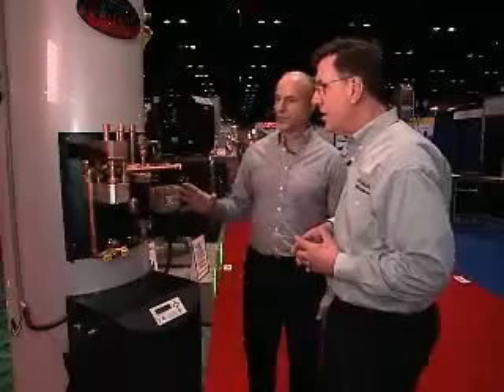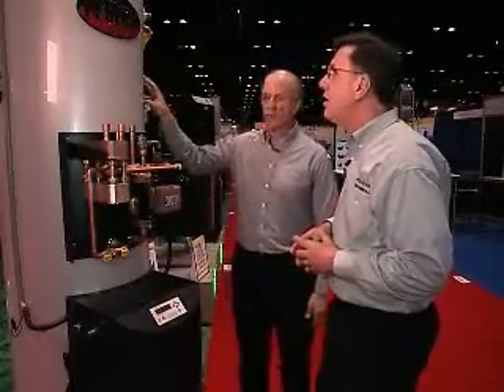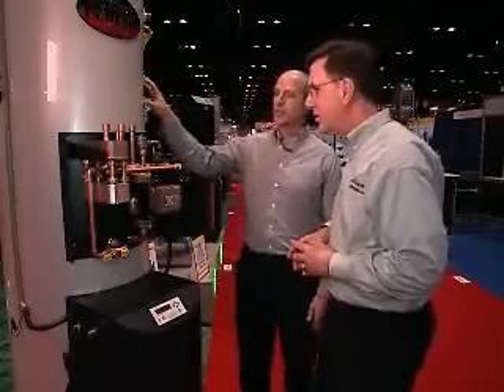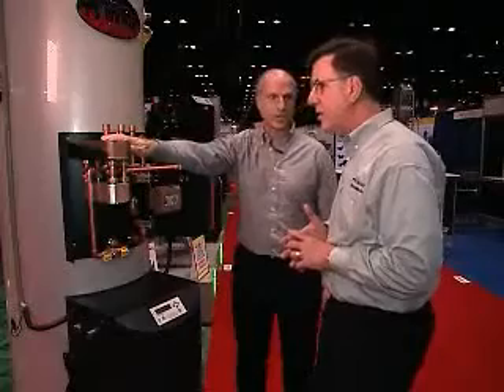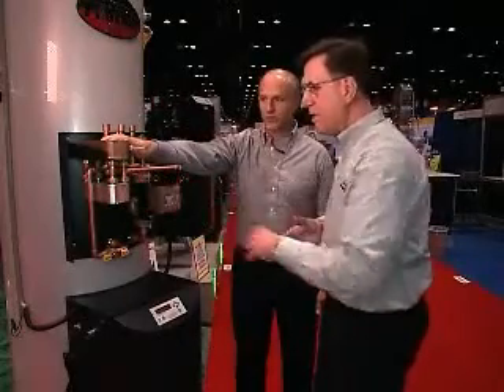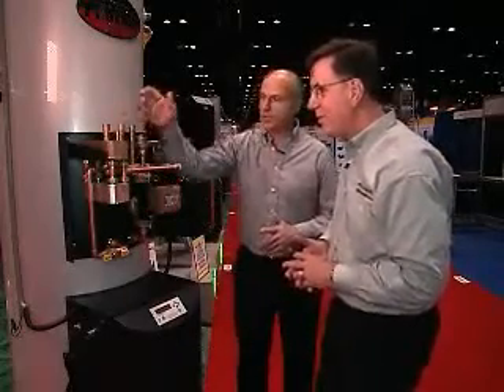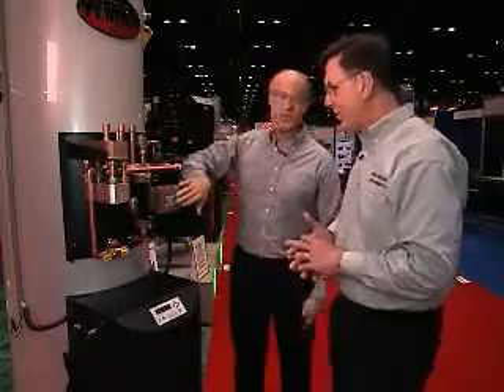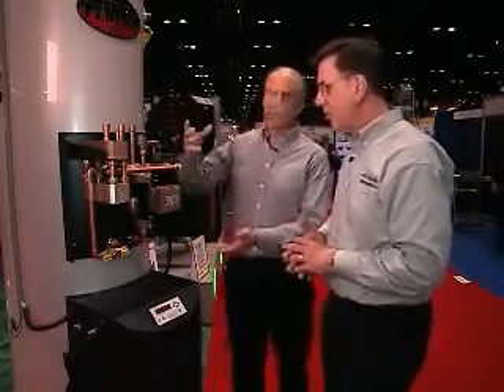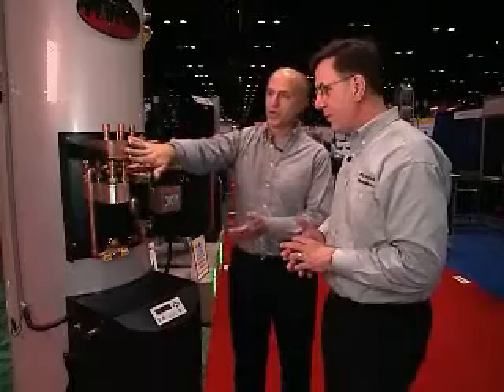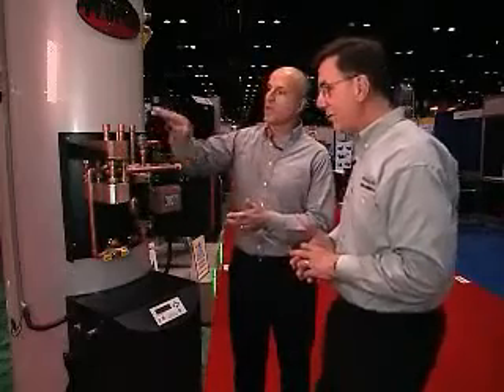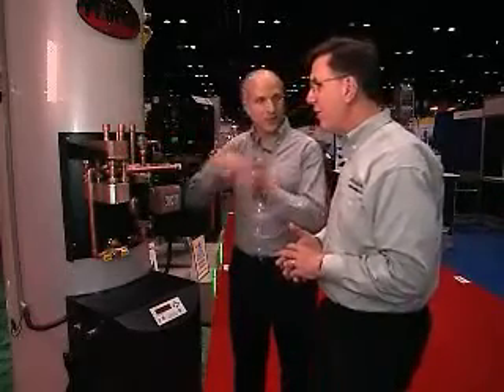We got the cover off, so we can show you how it physically works. We're taking the water from the storage tank and putting it through this plate and frame exchanger. Okay, and there's two of them? There's two of them, so we get extra output. And we have a variable speed pump. So we draw the water from the tank, put it through this plate and frame exchanger, and we backfeed the space heating. A little bit different concept.